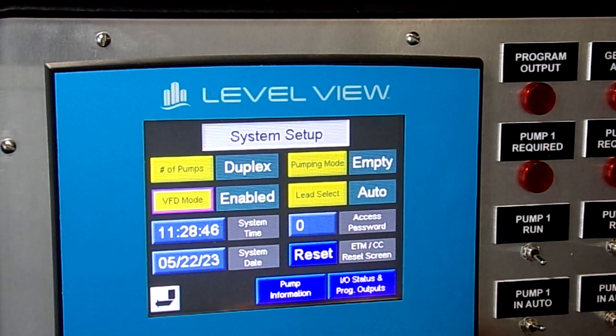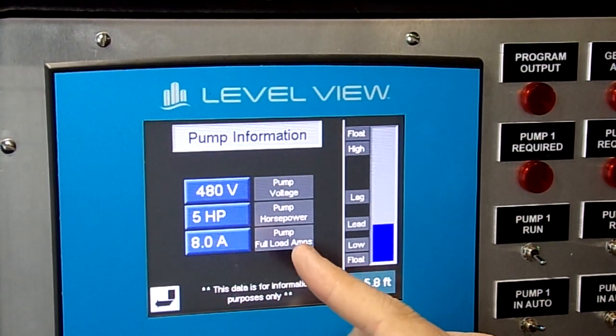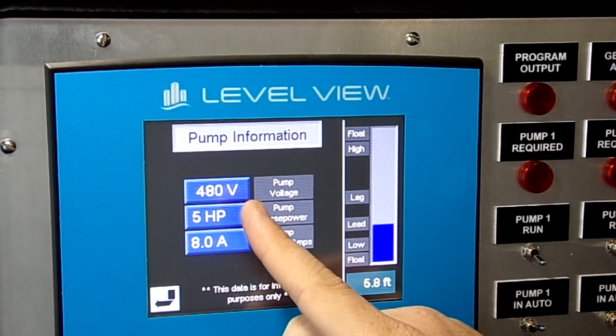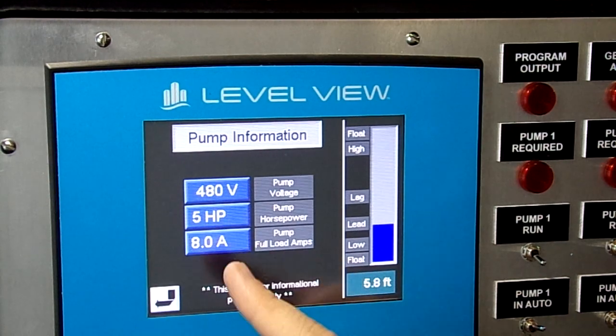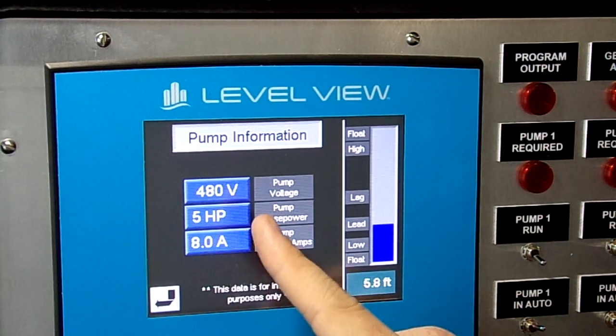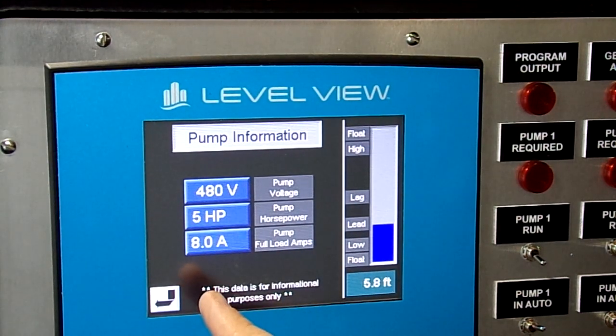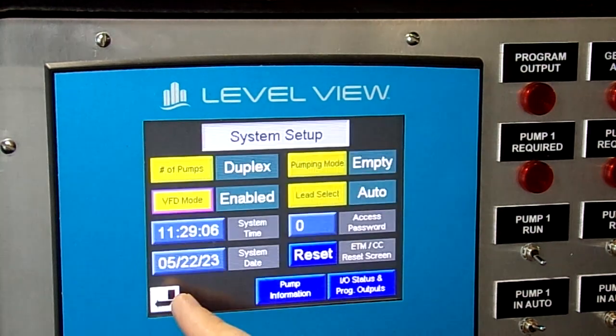Your date and time will be on this screen, as well as resetting your ETMs or your cycle counters. Your pump information can be entered at this click of a button. You can insert your 480 volts, your 5 horsepower, and the FLA for your station. This is all manually controlled and can be set up for each station individually.